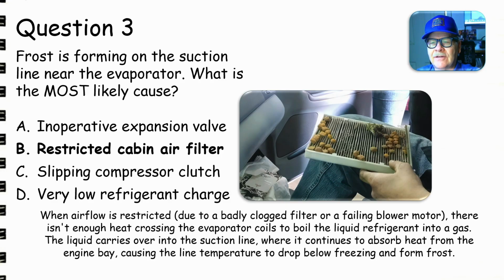There's not enough heat crossing the evaporator coils to boil the liquid refrigerant. The liquid carries over into the suction line and continues to absorb heat in the engine bay, a lot of heat, more than normal, causing the line temperature to drop below freezing and form ice.